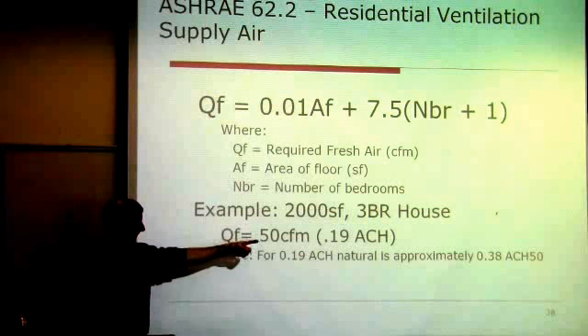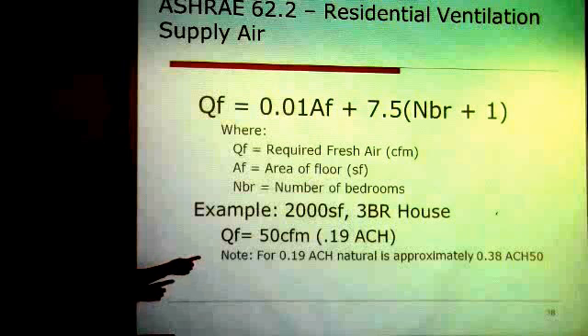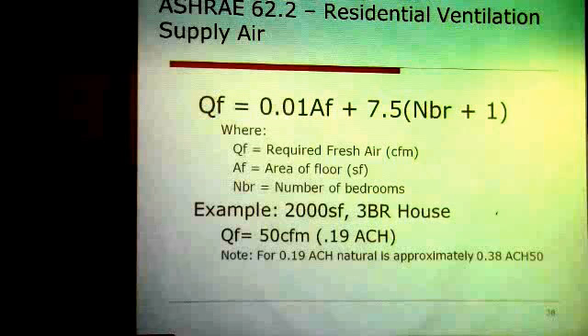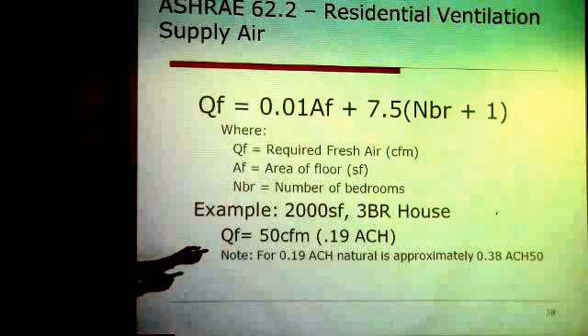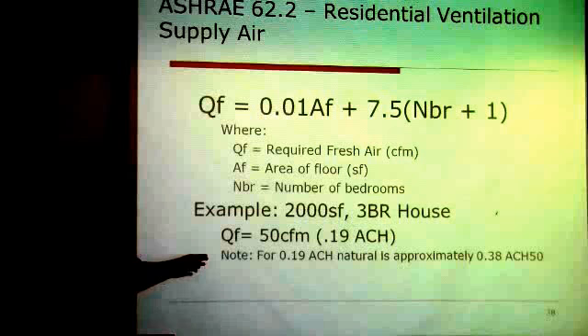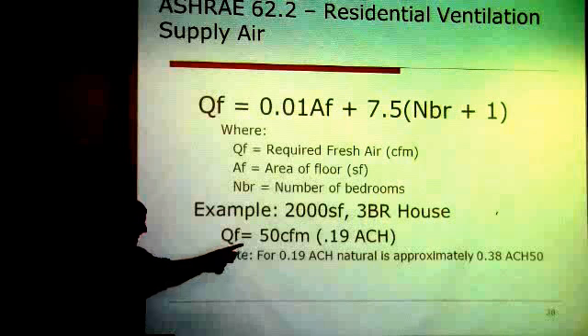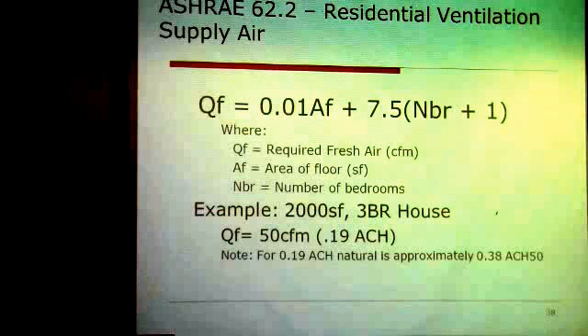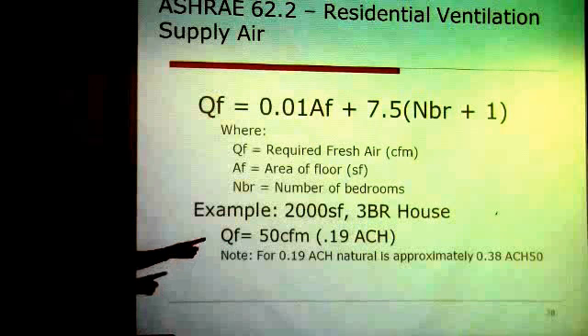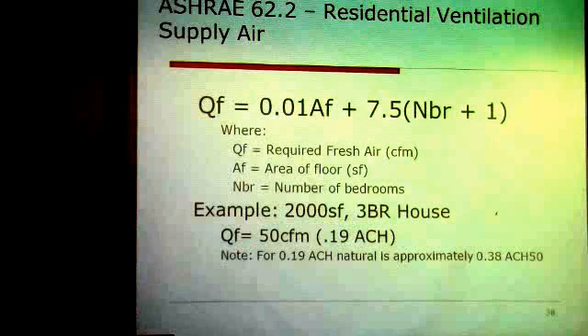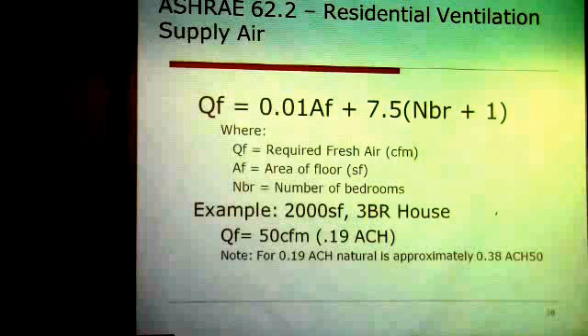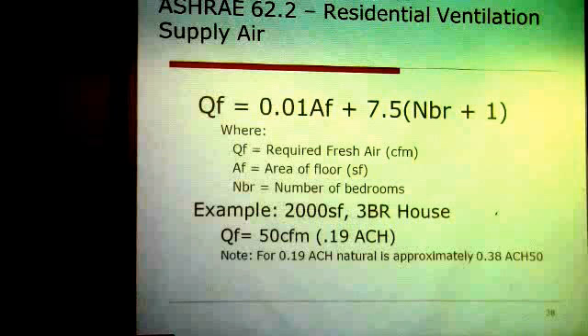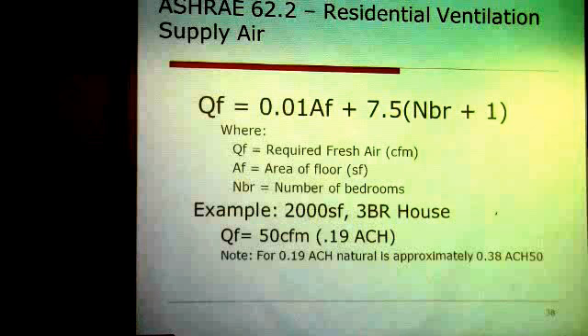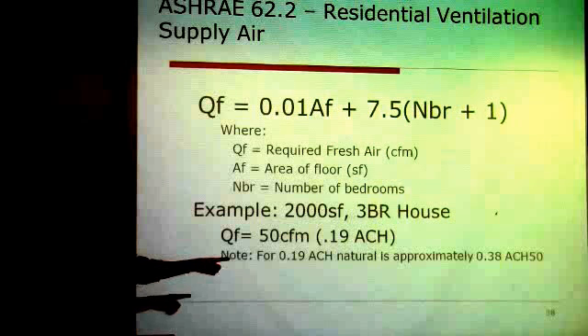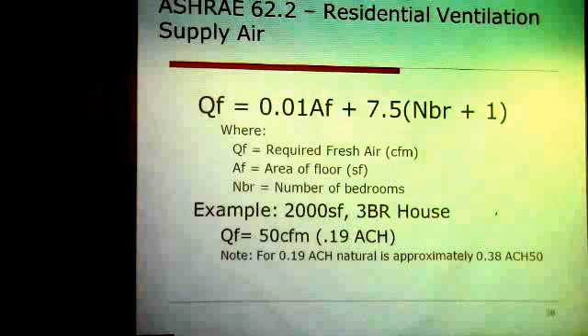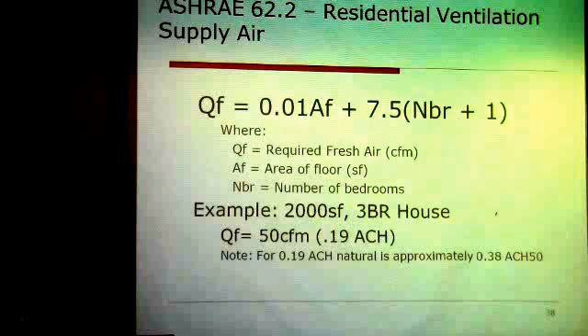And that equals, for this example, an air change rate of 0.19. If you do 50 CFM and look at your volume of air, you're getting an air change rate of about a fifth of the air change an hour. And then, as briefly talked about before, trying to change that to what it would be at ACH 50. So 0.19 is a minimum required in this house, and that relates to about 3.8 air changes at 50 pascals. Like I said, that's about an average. You can go higher or lower depending on if you have a higher building or more wind exposure. But it's just saying if you're below... or actually, it should be 3.8. I think, is that right?